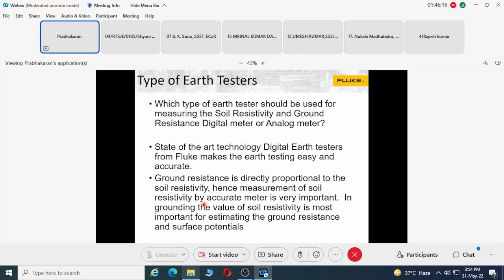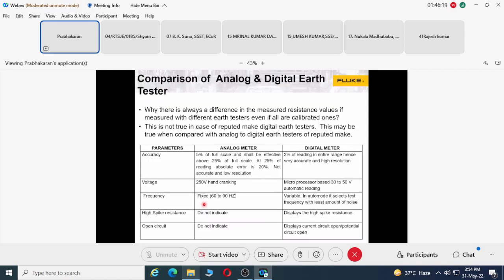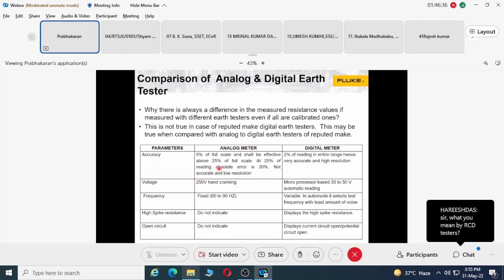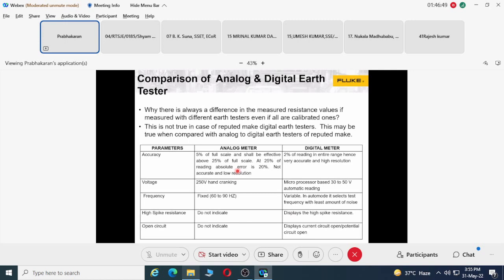What happens when you use this product, whether analog type or low cost type? Here is a quick comparison of analog meters and digital meters. Usually analog meters come with very poor accuracy, and it can affect 25% of full scale error. This means when doing testing with analog instruments, you may end up getting very wrong, confusing readings. That's why we always recommend a digital meter.